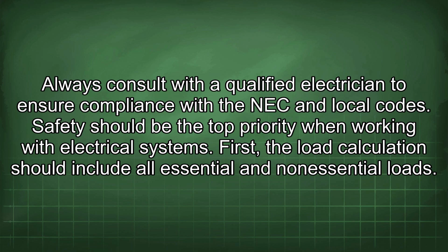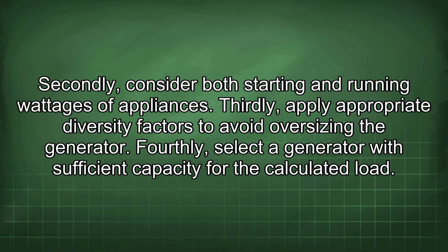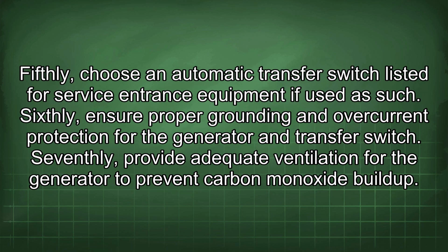First, the load calculation should include all essential and non-essential loads. Secondly, consider both starting and running wattages of appliances. Thirdly, apply appropriate diversity factors to avoid oversizing the generator. Fourthly, select a generator with sufficient capacity for the calculated load. Fifthly, choose an automatic transfer switch listed for service entrance equipment if used as such. Sixthly, ensure proper grounding and overcurrent protection for the generator and transfer switch.